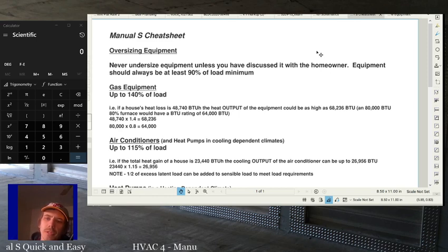Okay, what's the temperature in the house? It's 74. What do you got it set at? 70. Okay, well, if it's 100 degrees outside, and the equipment can get down to 74, that's pretty good, right? For our area, for what we designed the equipment for. If it's running all day and it's keeping it at 74, that's actually better than what it was designed for. So that would be normal, all right? You can always double check and make sure there's nothing else that would improve the cooling performance, but that would be normal. That would be a good thing, right?